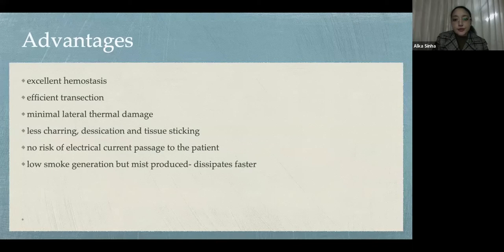The advantages of using these ultrasonic surgical devices are excellent hemostasis, efficient and precise transection of the tissues, minimal lateral thermal damage, less charring, desiccation, and tissue sticking to the jaws of the forceps. There's no risk of electrical current passage to the patient, and less smoke generation compared to traditional electrosurgical devices. However, a fine mist is produced, which sometimes interferes with visibility, but it dissipates much faster than the smoke plume produced by other instruments.